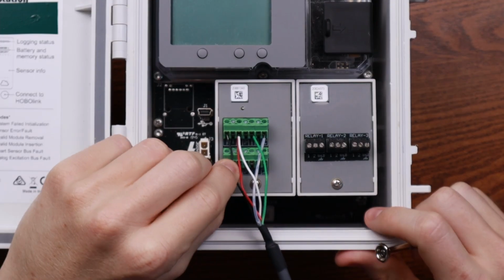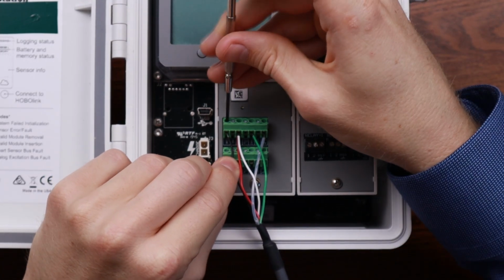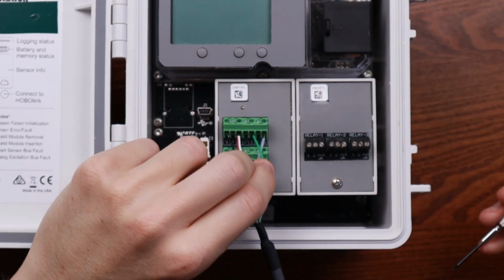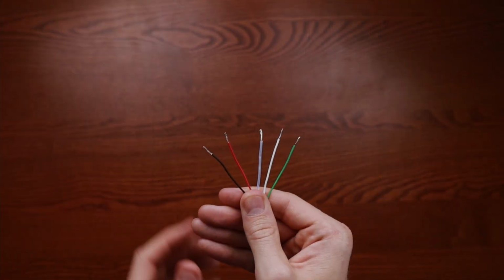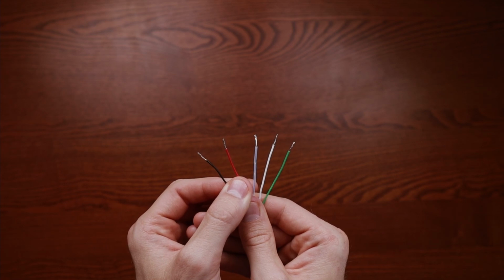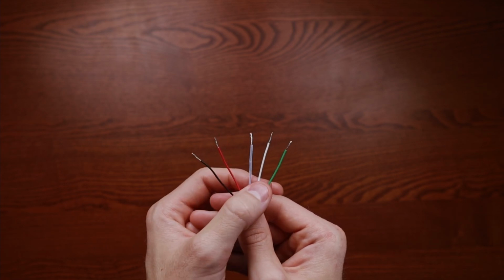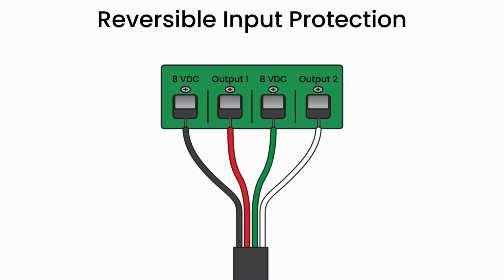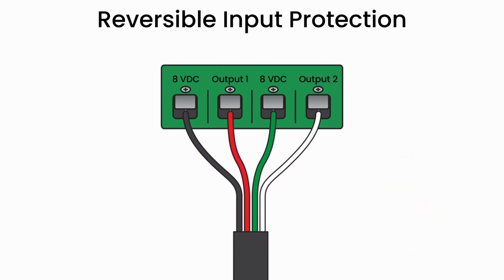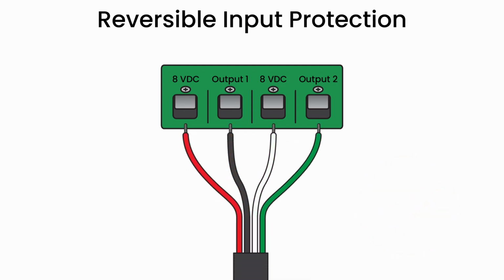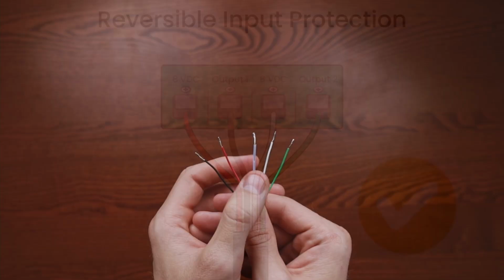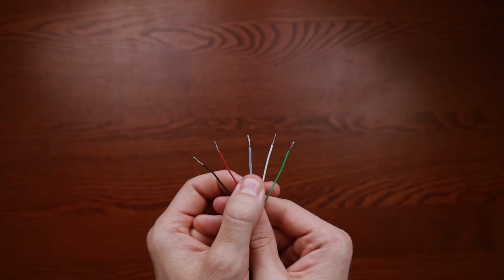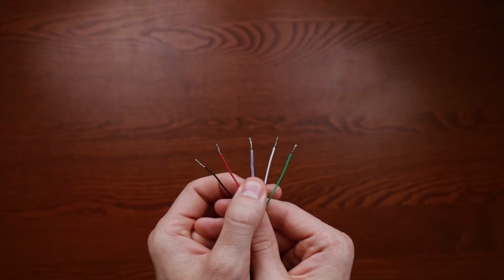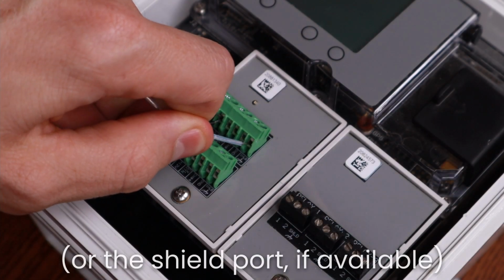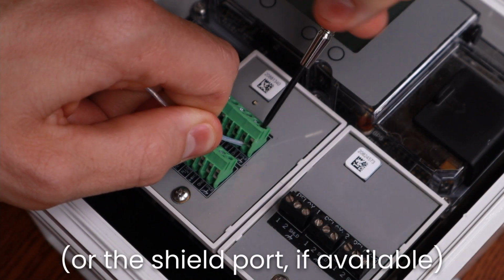To start with, let's check the wiring. Inspect it to verify that the connections are secure and there are no signs of water damage. To review, the red and black wires are for the main parameter, while the green and white pair are for temperature. Both pairs are reversible, meaning either can act as the power or output connection. The last thing to note is the clear coated shield wire, which we always recommend installing to ensure accuracy. Connecting it to ground may solve any issues involving erratic readings.